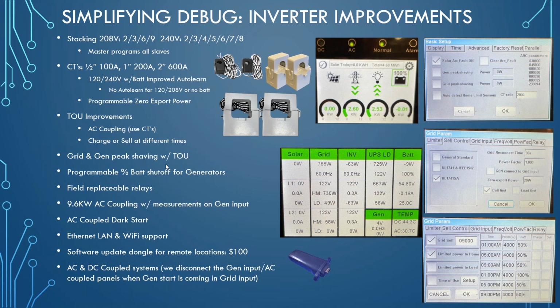Well, we fixed that with software as well, where we leave a little bit of a buffer in the battery when we shut down, if you do hit the lowest range of your battery. Then in the morning, and we do this in an intelligent way, we don't just do it every 2 hours, we wait till the sun will probably be up, and we'll fire up the inverter and look for the AC coupled panels. If we find them, great, we power back up, charge batteries, and we're good to go automatically. If we don't find the AC coupled panels, maybe it's still super cloudy, we'll turn back off again and try again in an hour or two. All automatically, so you don't have to worry about it.